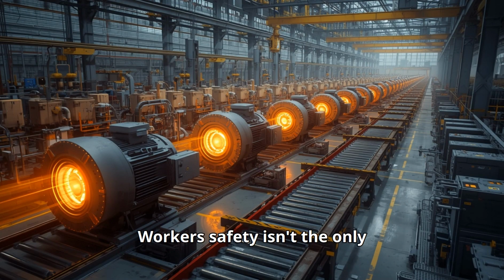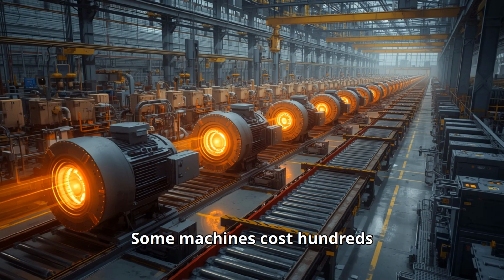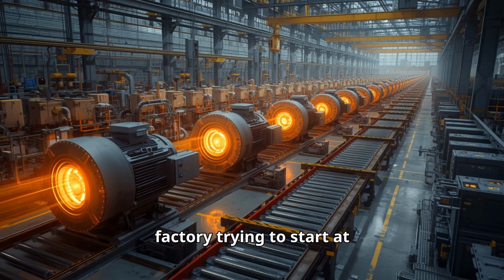Protecting equipment? Worker safety isn't the only reason. Industrial equipment is extremely expensive. Some machines cost hundreds of thousands of dollars. Others cost millions. Imagine every motor in a factory trying to start at exactly the same moment. The electrical demand would be enormous. Large motors draw several times their normal current during startup. If dozens of them started simultaneously, voltage could collapse, circuit breakers might trip, transformers could overload, sensitive electronics could fail. Instead, engineers carefully sequence the startup process. This reduces electrical stress and protects the entire power system.